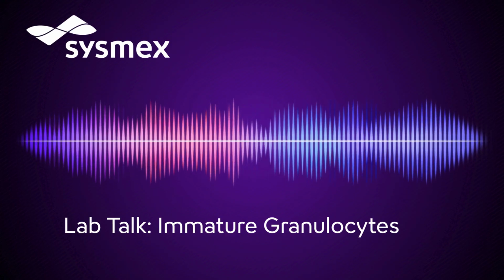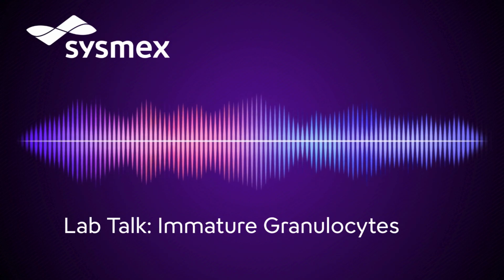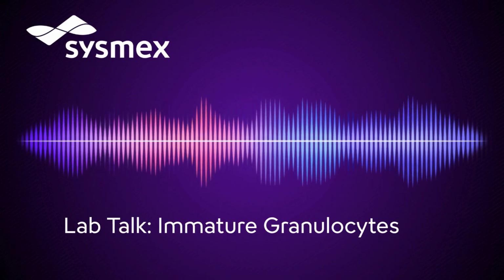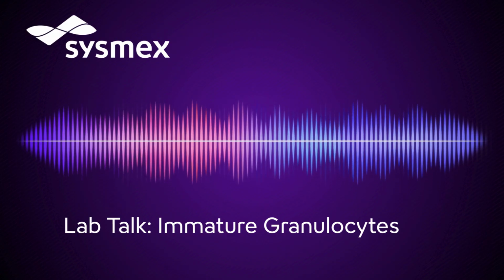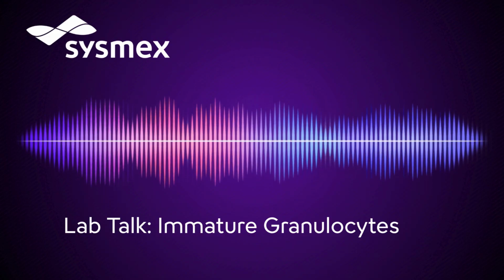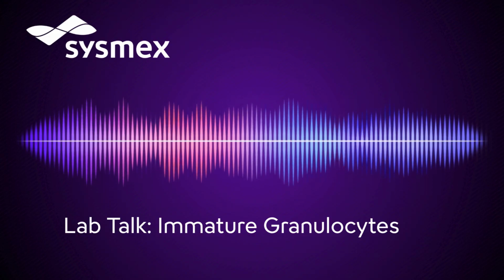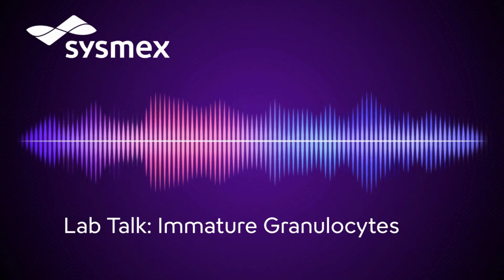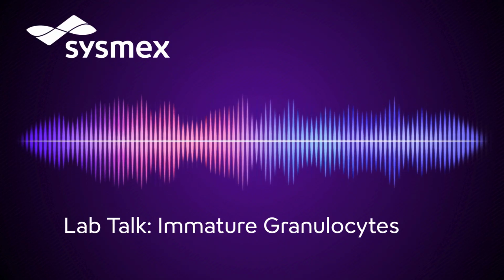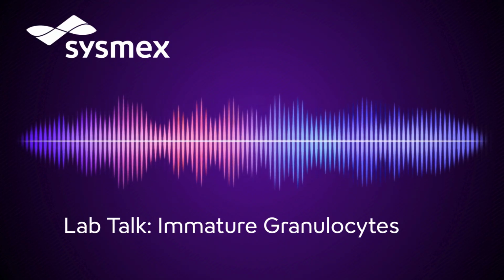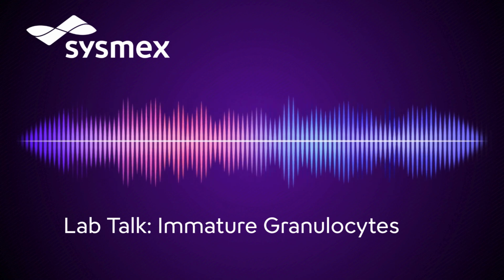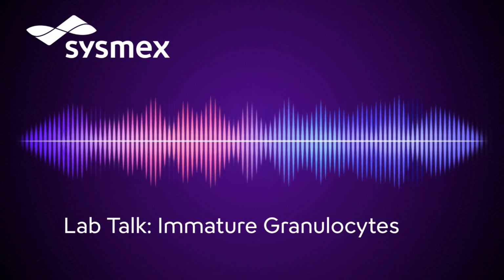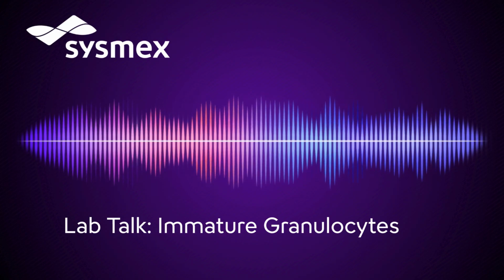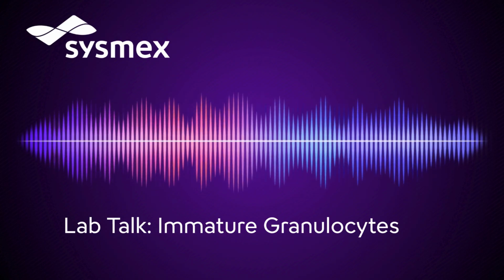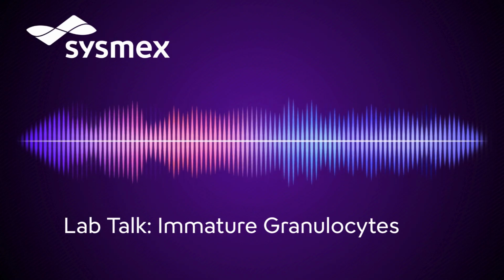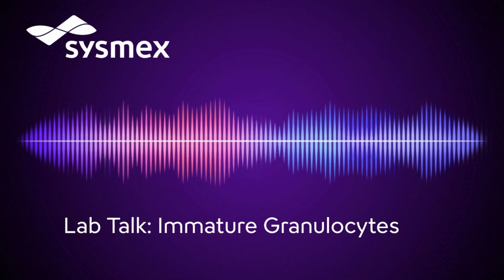All right, let's wrap this up with a quick recap. IG includes promyelocytes, myelocytes, and metamyelocytes, which are early granulocyte precursors. IGs are normally absent in peripheral blood, but their presence indicates a left shift which may be associated with infection, inflammation, or bone marrow disorders. Sysmex analyzers use fluorescence flow cytometry to provide automated, highly sensitive, and standardized IG measurement with every automated differential. Automated IG% and absolute counts can improve lab efficiency by reducing manual reviews.